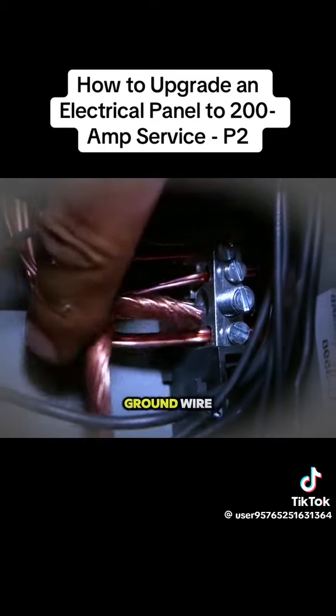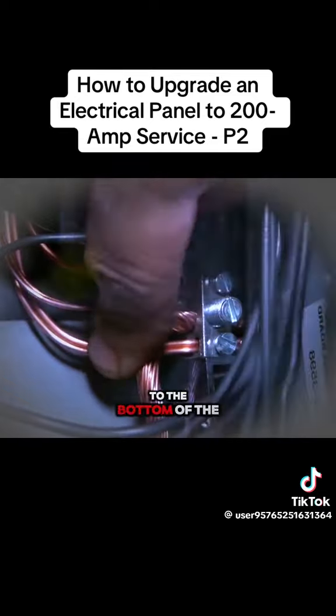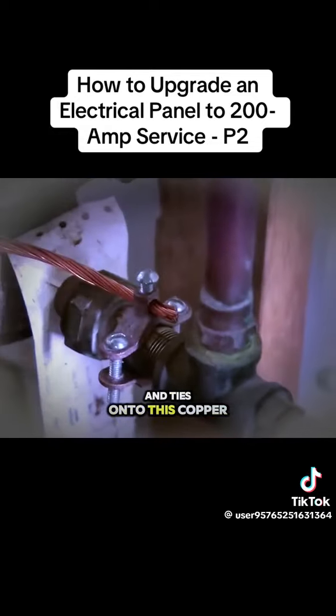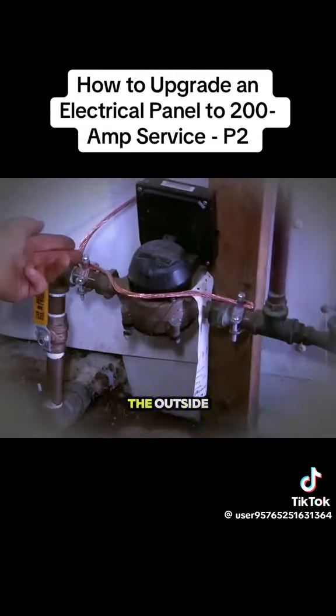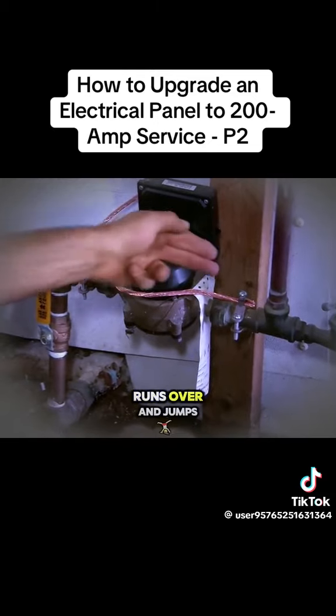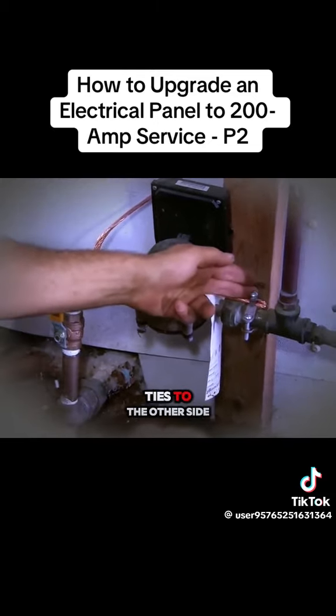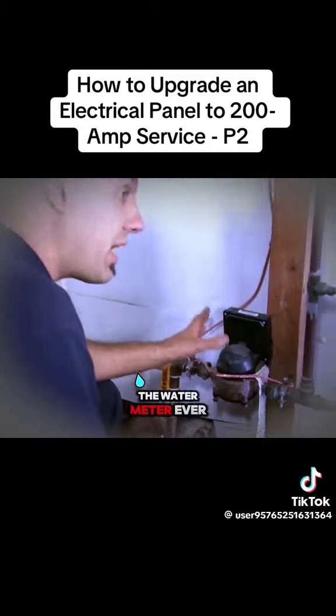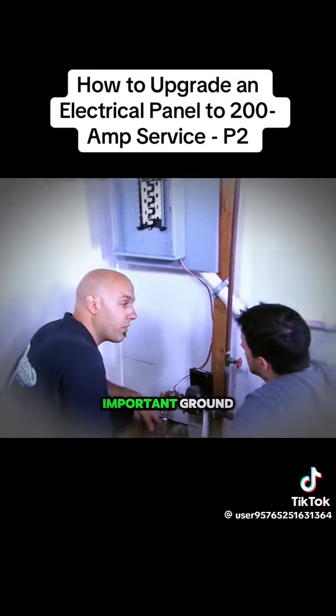This is your main ground wire. This wire runs out through the bottom of the electrical panel and ties onto this copper water main that comes in from the outside. I got a clamp, runs over and jumps your water meter, and ties to the other side. That way, if the water meter ever gets removed, you'll always have this important ground.